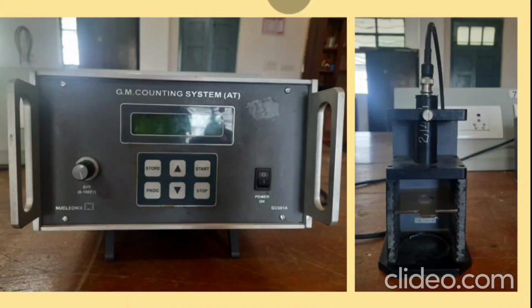Let us see what is a Geiger-Muller counter. Geiger and Muller developed a particle detector for measuring ionizing radiation in 1928 and they named it as Geiger-Muller counter. Ionizing radiation include alpha particles, beta particles and gamma rays. A GM counter can count individual particles at rates up to about 10,000 per second and they are widely used in medicine and in prospecting for radioactive ores. This is the picture of GM counter which we will be using in our experiment.